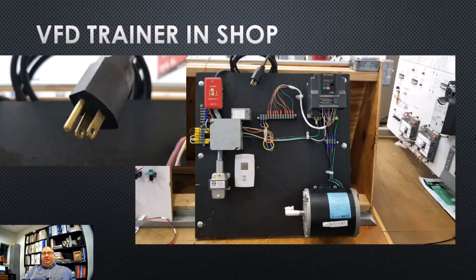This is the VFD board. As you can see here, it's on a 115 outlet plug, and it controls a 3-phase motor over here that's rated for 208/230. We have a little relay here. The relay is called the pilot relay, and it will initiate the start-stop command to the drive. We have a thermostat here, basically a normal stat. G will make at the stat, G will feed to the relay, and then from the relay we pilot the operation with a discrete input point: start, stop, run, forward. Then we configure the drive for the nameplate information. Pretty simple, but yet effective.